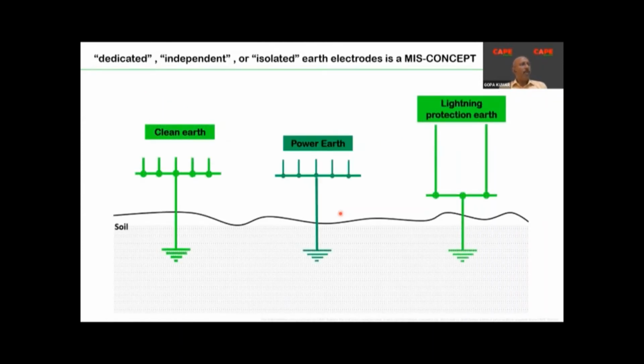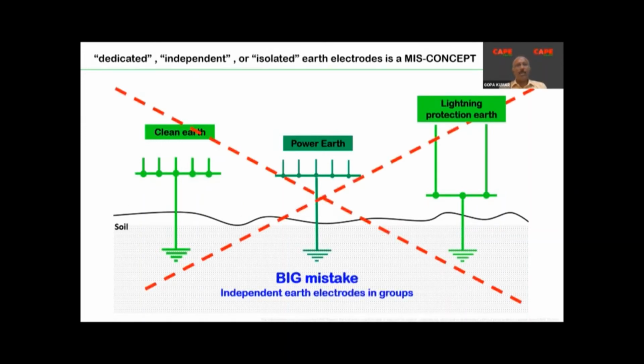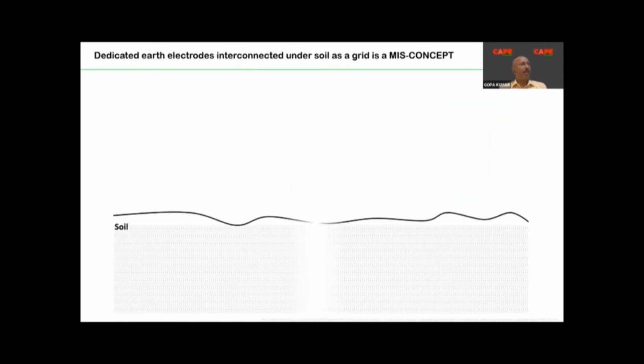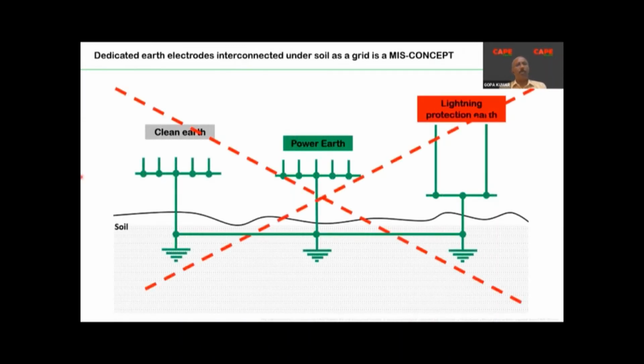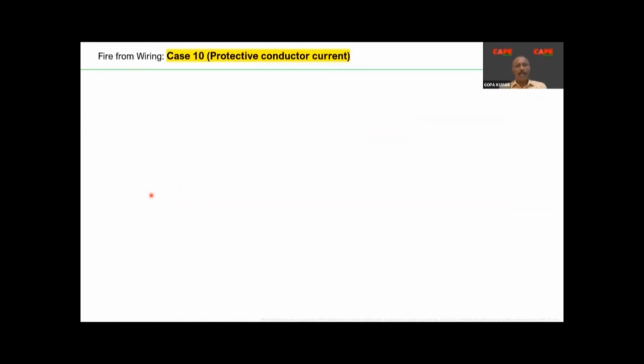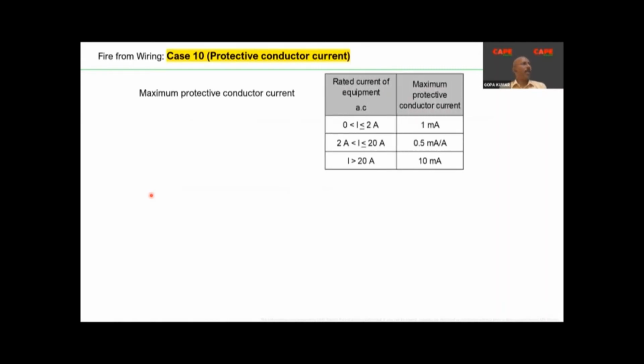People also follow a different system like a clean earth, power earth, lightning protection system earth. This is also a big mistake. These are never written and documented in any standard. People also make the third mistake. You put a separate earth electrode in soil and interconnect everything under the soil. This is also a mistake. Probably sometimes this is okay for shock hazard, but for fire, of course, this will not work. So the previous picture which I have shown, that is the right way in case 9. I can share the presentation if you require, so that you can go through it later.